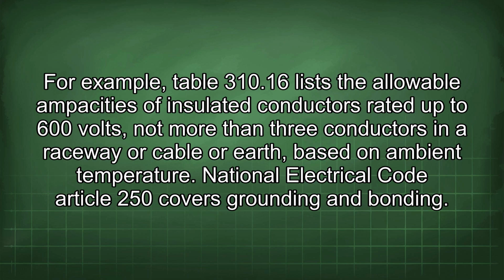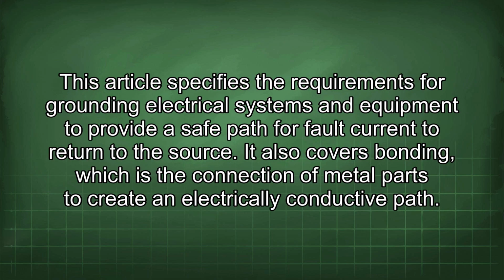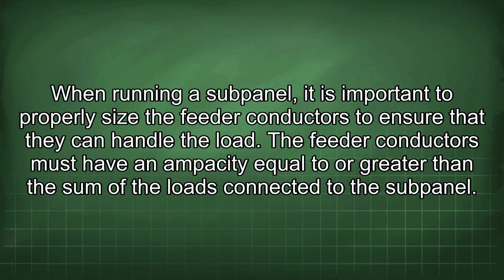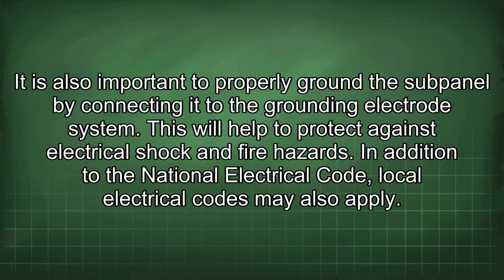National Electrical Code Article 250 covers grounding and bonding. This article specifies the requirements for grounding electrical systems and equipment to provide a safe path for fault current to return to the source. It also covers bonding, which is the connection of metal parts to create an electrically conductive path. When running a subpanel, it is important to properly size the feeder conductors to ensure that they can handle the load. The feeder conductors must have an ampacity equal to or greater than the sum of the loads connected to the subpanel. It is also important to properly ground the subpanel by connecting it to the grounding electrode system. This will help to protect against electrical shock and fire hazards.